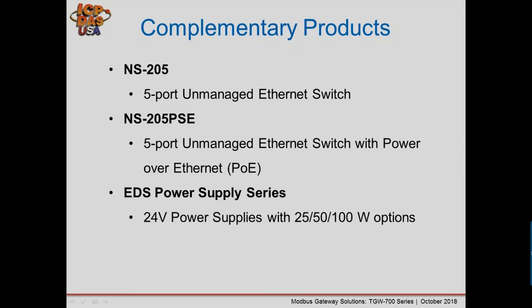Complementary products include the NS205, a five-port unmanaged Ethernet switch for environments without existing Ethernet infrastructure. The NS205 PSE version supports PoE — supply 48 volts DC and it passes power to TGW modules. EDS power supplies are also available, providing 24 volts DC in 25, 50, and 100 watt options.